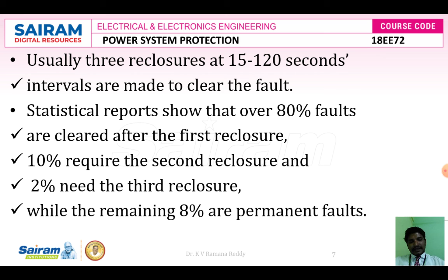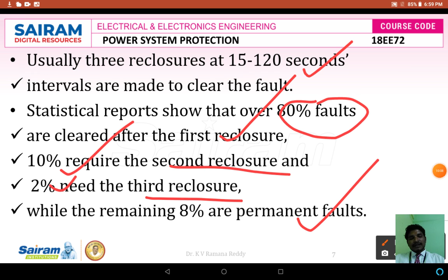3 reclosures means it takes a time interval of about 15 to 120 seconds. So between that 15 to 120 seconds we have to clear the fault. Most of the faults are cleared at the first reclosure, that is 80% of the faults are cleared in the first reclosure. Only 10% of the faults are cleared at the second reclosure, and 2% of the faults are cleared at the third reclosure, while the remaining 8% of the faults are permanent faults. These are the statistics especially on the 33 kV transmission system.